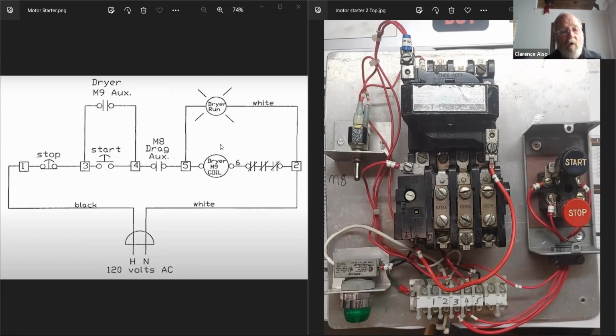Now you want to go to number 4. You're expecting 120 volts there when? When the start button's pressed. Terrific. So I'm telling you, you got 0 volts there. Not a good reading, is that right? Not a good reading, no.